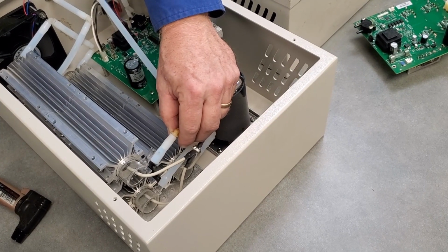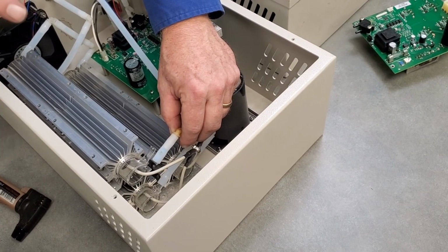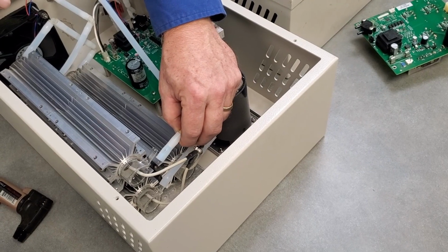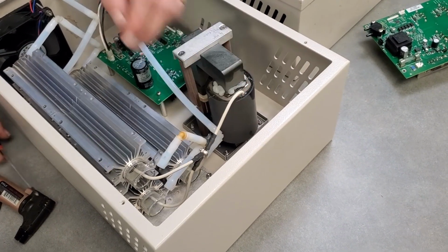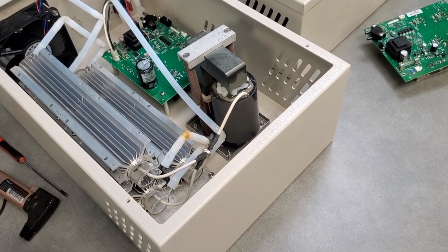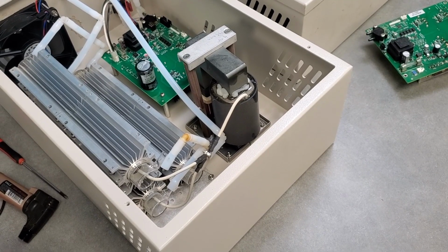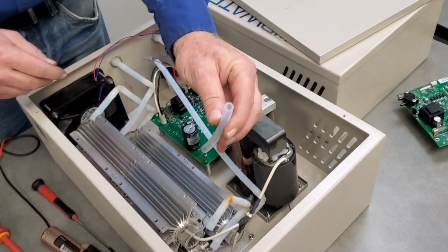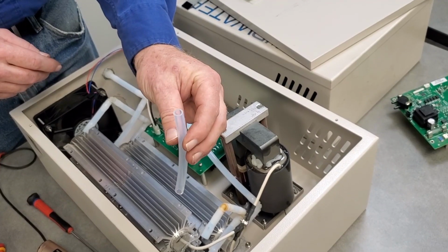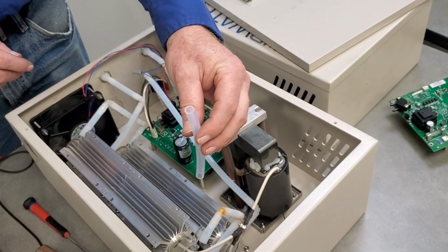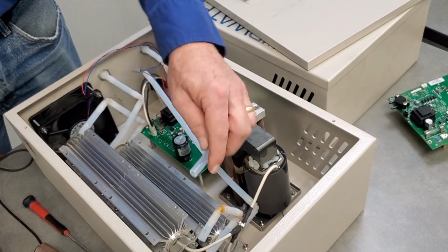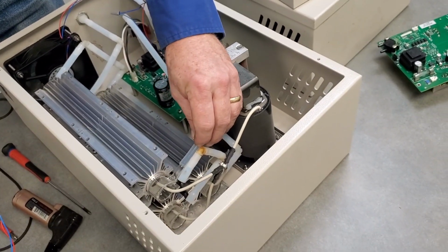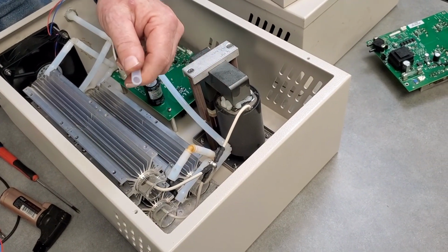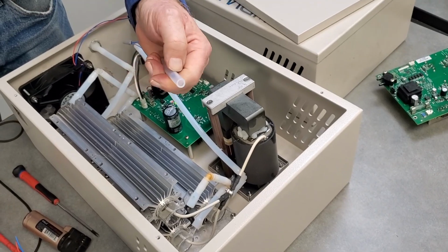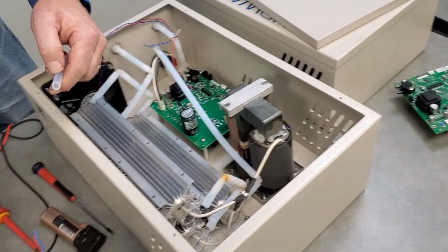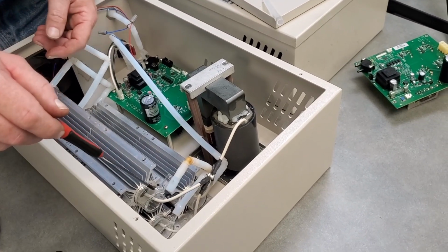Alright, so as it cools and contracts, it makes a really tight seal on that nipple. The new tubing is FEP tubing. It's 1/4 inch inside diameter, 3/8 outside, so it's rather thick. And to get it on there, it just doesn't fit. So the best option is to heat that up and expand it a little bit.